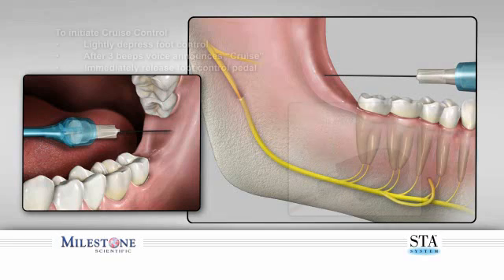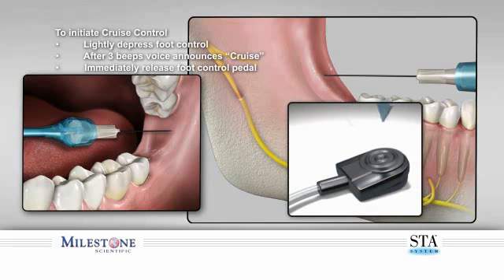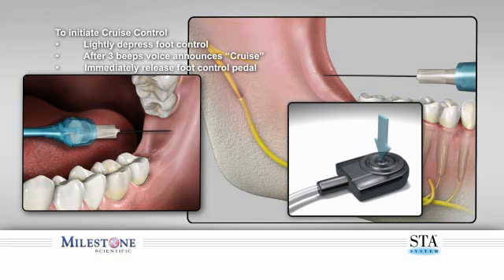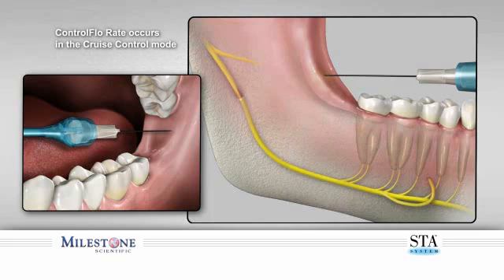To initiate the injection using cruise control, slightly depress the foot control. After three beeps, you will hear the STA system announce "cruise." Immediately release the foot control pedal to enter into the cruise control mode. This allows the ControlFlo rate to continue to dispense anesthetic solution, creating an anesthetic zone in front of the tip of the needle.